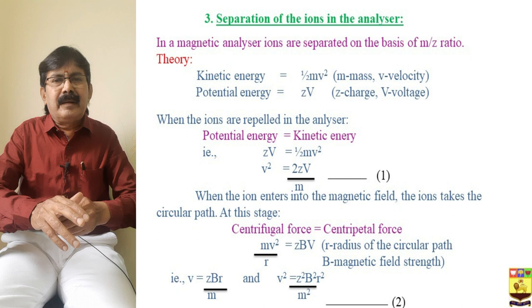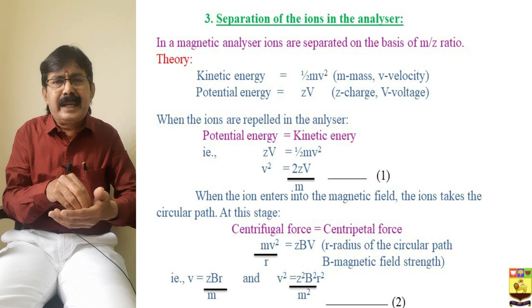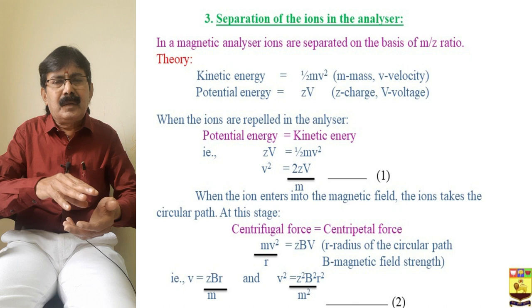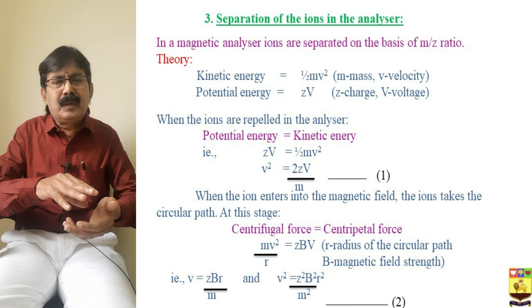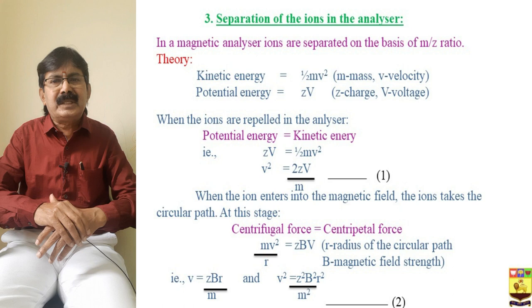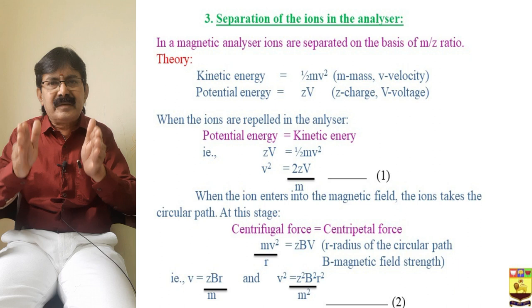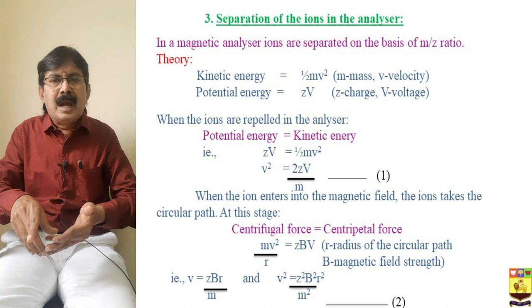To explain the analyzer, we need some theory. In the magnetic analyzer, because of the acceleration given in the ionic source, the ion acquires kinetic energy equal to ½mv². This must equal the potential energy associated with the molecule, given by zV. So when the molecule leaves the ionic source, zV = ½mv², and by rearrangement v² = 2zV/m — that is the first equation. This applies in the first field-free region before entering the magnetic field.